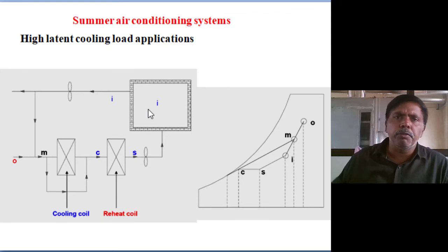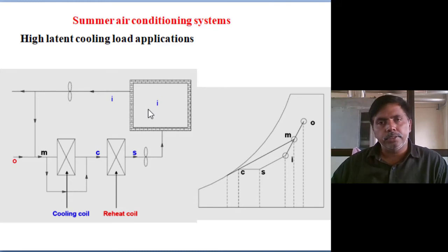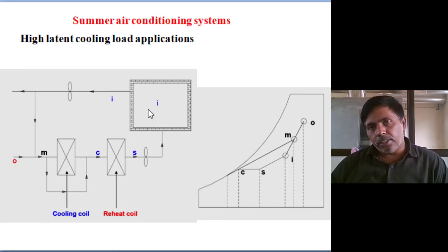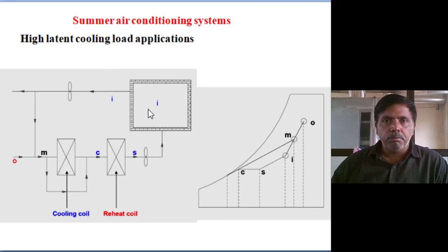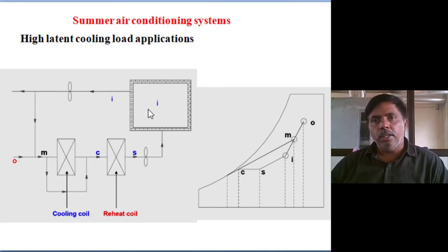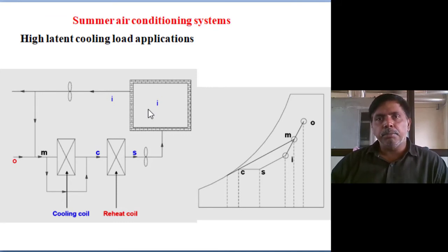At the time of opening windows, fresh charge is replaced. In general commercial areas, cinema halls, they are not substituting the fresh charge every time. But as an engineer, we have to propose at least 10%, 20% of the fresh charge to substitute every cycle.